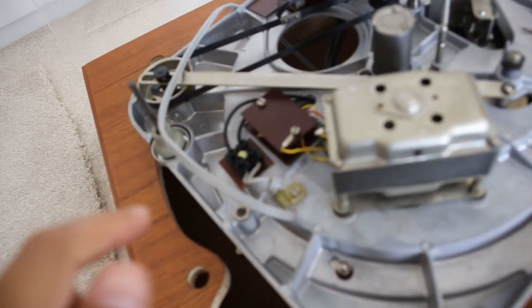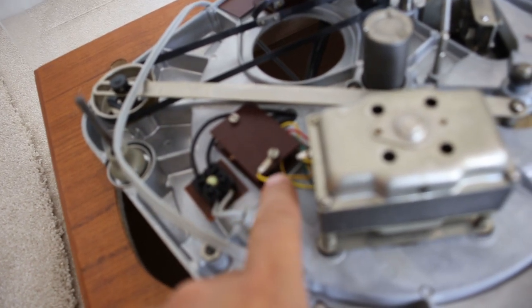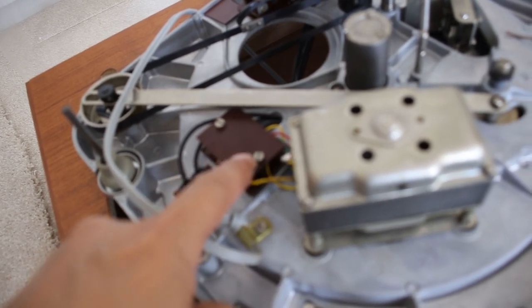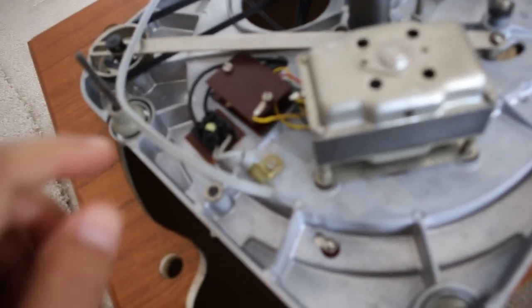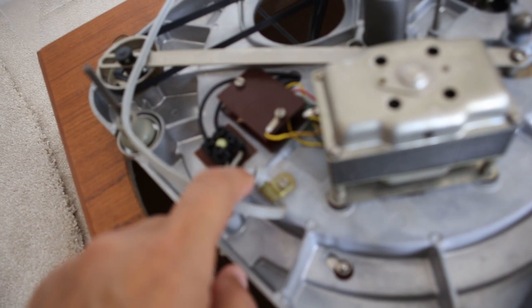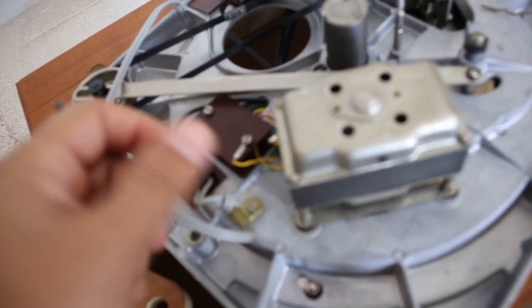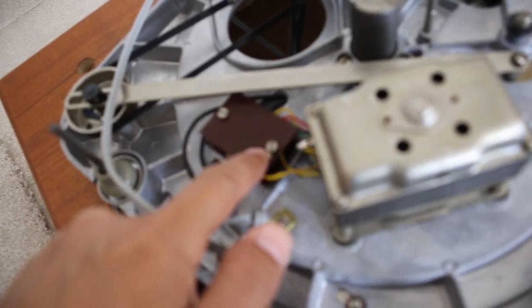If you take a look, here's the terminal block. Yes, there's two wires going in, but a modern three wire connection has an earth. Now if you take a look to the right of that terminal block, there's actually an earth connection here—this yellow wire from the E50 motor onto the chassis, so it's like a chassis ground or earth. We're going to use the third wire from our new mains cable and we're going to create an end to that earth wire with that eyelet or spade, and then what we're going to do is we're going to connect it along with this earth connection here.